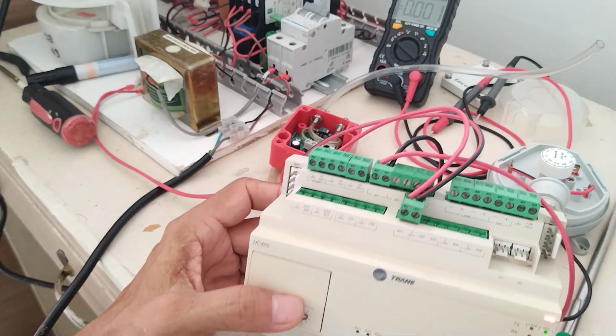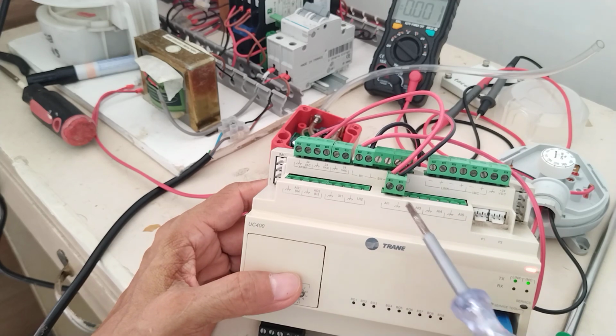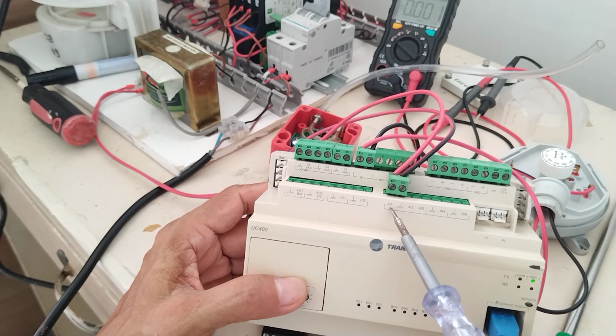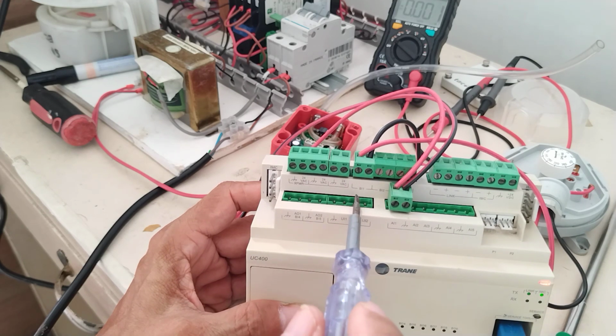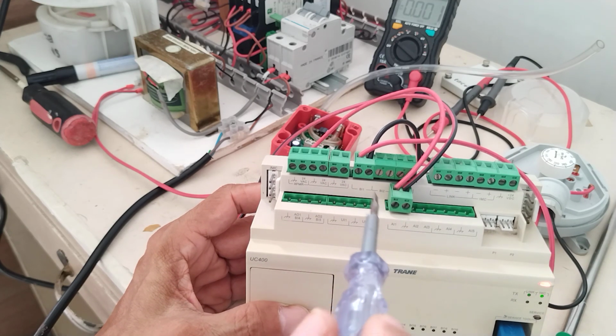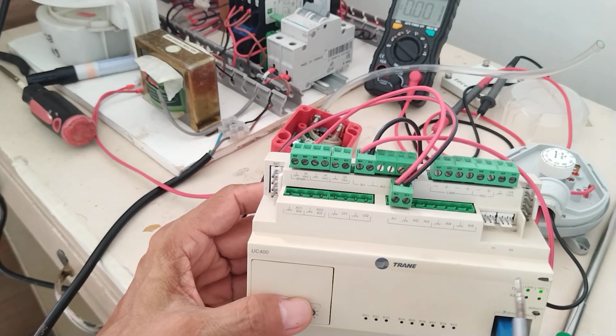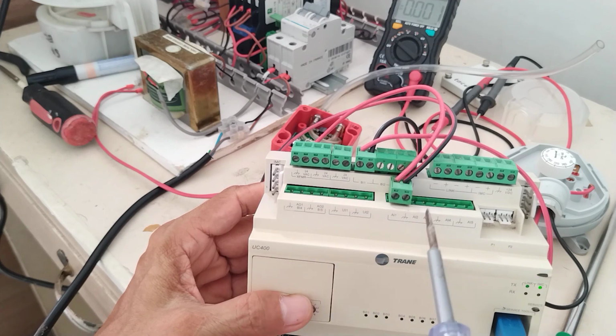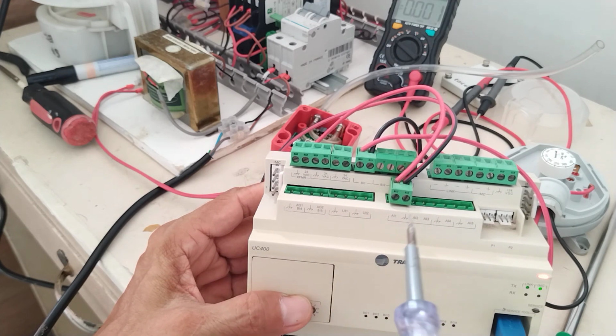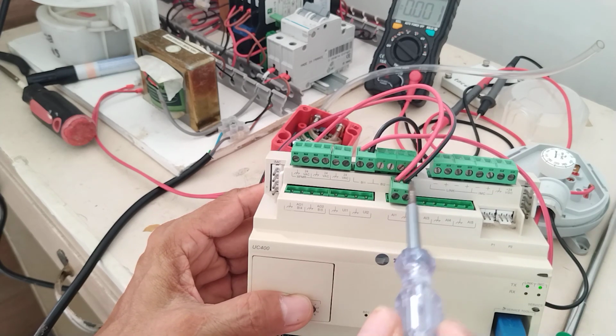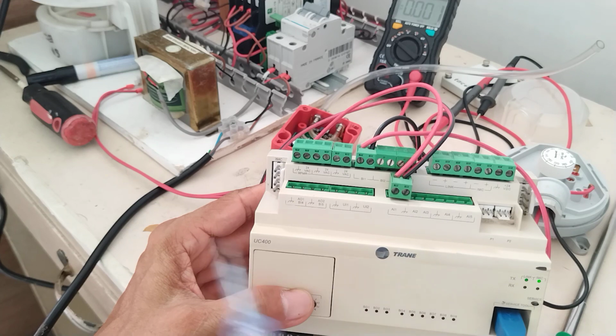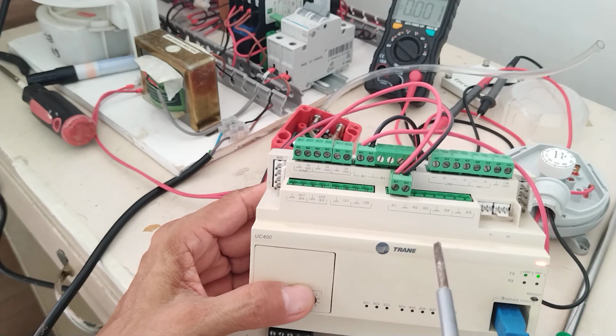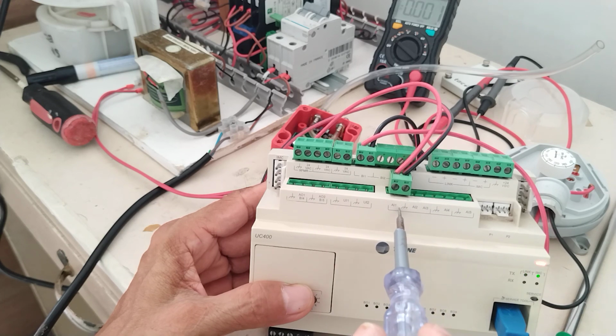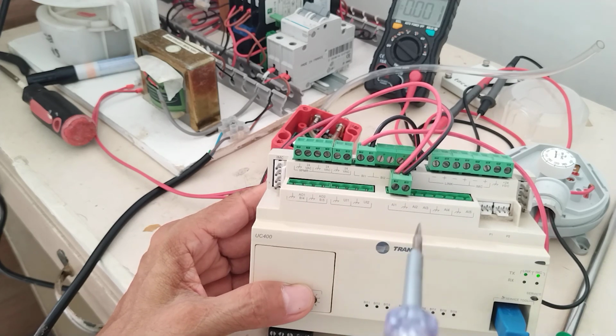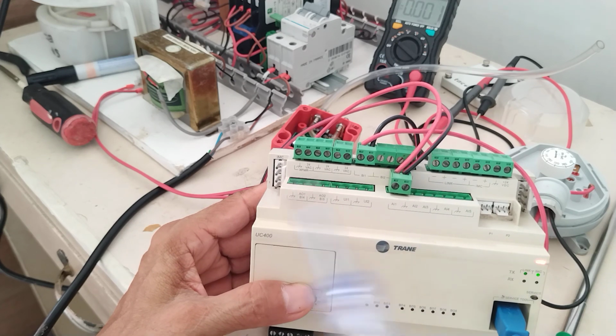Okay? Now, this is not enough. You need to do some configuration. Because analog input, you need to configure the channel. You can call this also binary input 1, input channel 1. So, binary input channel 2. Okay, so meaning you need to configure. For digital, no need to configure. But for the analog input, you need to configure it. Is it a voltage input? In this case, this is voltage input, 0 to 10 volts. Because there are some differential pressure transmitters where the output is current. So you will have to configure it if it is a current input. Or is it a temperature input? Okay. So, there are several types of input. So, you need to configure it so that you will get the proper reading.